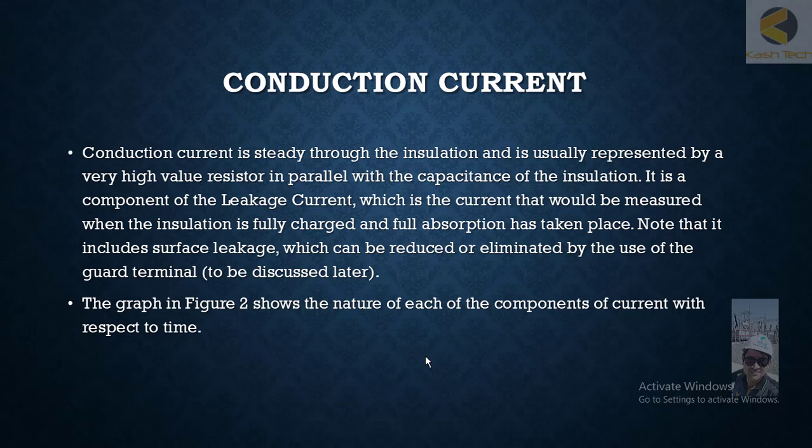This current basically depends upon the insulation resistance, which is a pure resistance of the insulation. You will get the correct reading once the charging current and polarizing current have finished — after some seconds, depending upon the time constant of the specific insulation — and the leakage current reading as well.